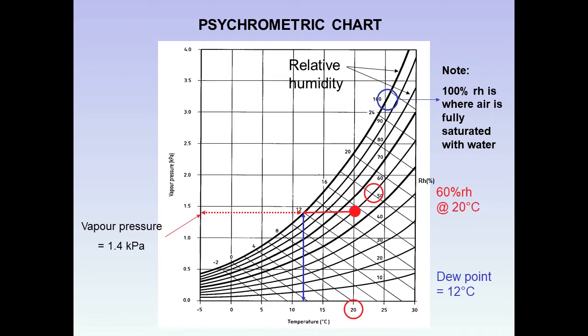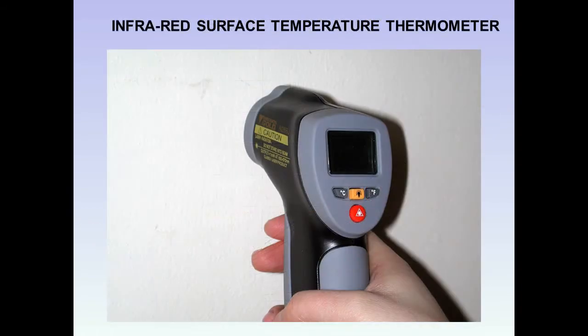So we now know that the dew point temperature is 12 degrees. What we have to do now is measure surface temperatures, and for this one can use an infrared surface temperature thermometer. If the surface temperature is above 12 degrees, then condensation will not be occurring. If it's below 12 degrees, then condensation will be occurring.